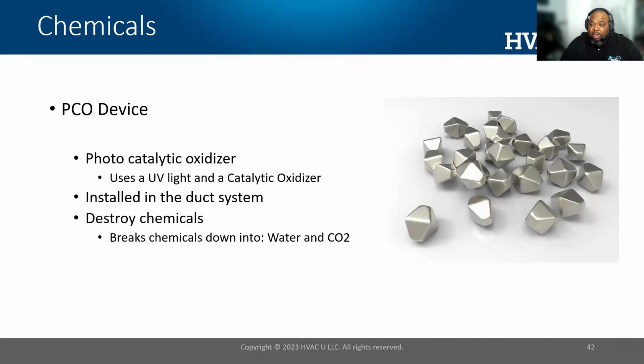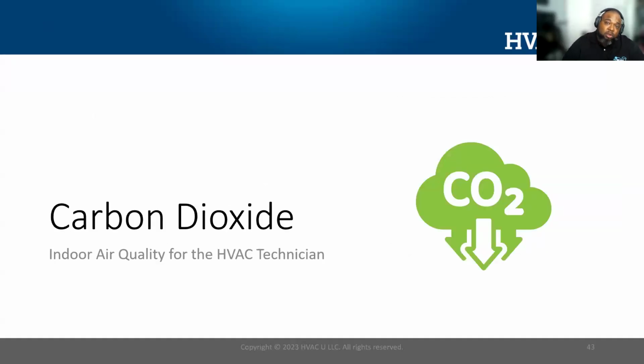They use a UV light and a catalytic oxidizer. They're installed in a duct system and they break it down into water vapor and carbon dioxide. And the reason why this is our least preferred method is because water vapor and carbon dioxide are also IAQ parameters that we're trying to control. Right? Which brings us up to our third one.